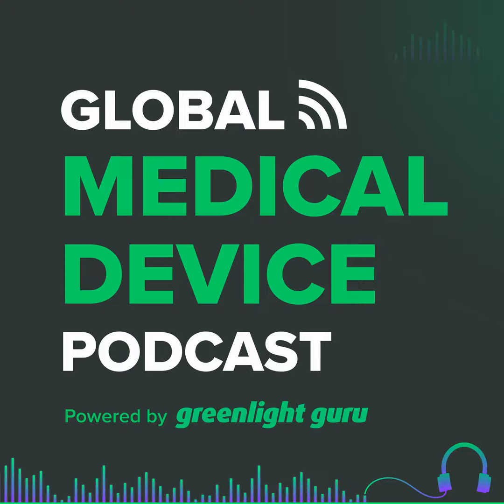We can put a link to that particular podcast, SR versus NSR devices, in the podcast notes if people are interested. The reason why it's applicable here is because if your device is a significant risk device or an SR device, then you are required to get an IDE or an investigational device exemption prior to beginning your clinical trial. If your device, on the other hand, is a non-significant risk device or NSR device, you're what we call IDE exempt. And in that case, there's no obligation for you to go to FDA to begin your clinical trial first. You still have to go to the IRBs. You always have to go to the IRBs, but not to the FDA.